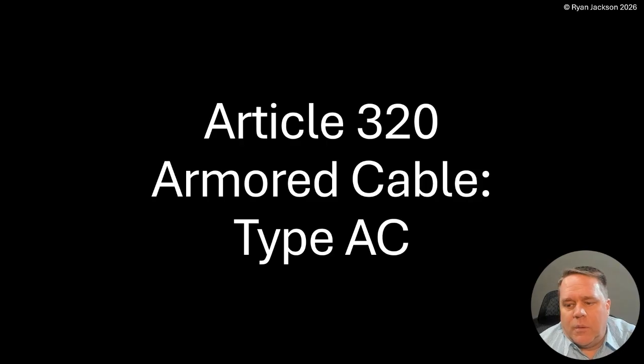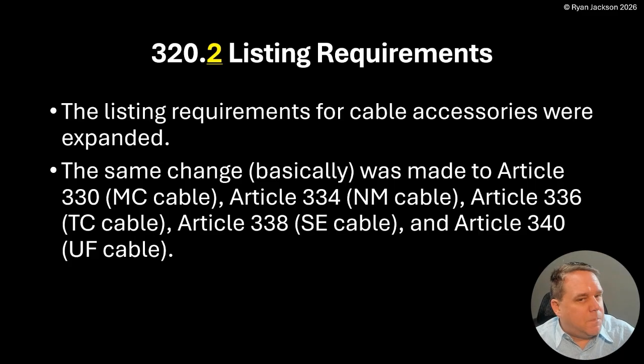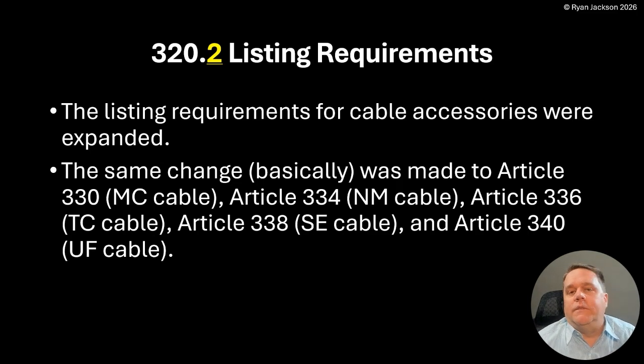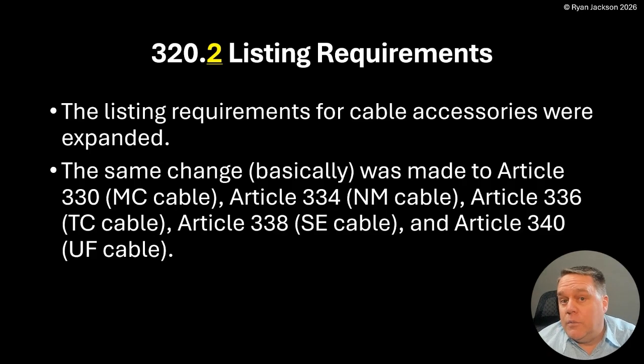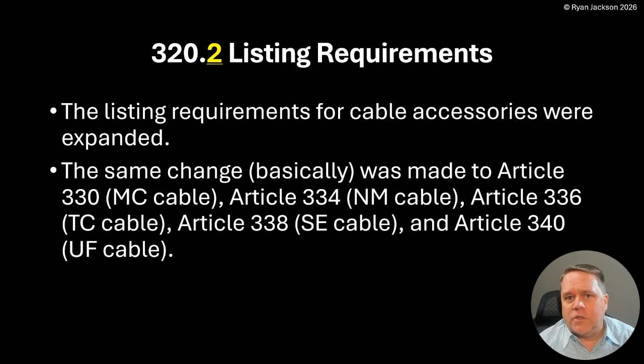Article 320 — Armored Cable, Type AC. Section 320.2, listing requirements: the listing requirements for cable accessories were expanded. Essentially the same change was made to Article 330 for MC cable, 334 for NM, 336 for tray cable, 338 for SE cable, and 340 for UF cable. There are a couple of small differences — for example, tray cable talks about cleats since it's usually in a cable tray — but for the most part the change is the same across all these articles.